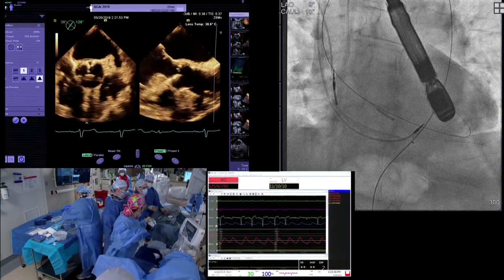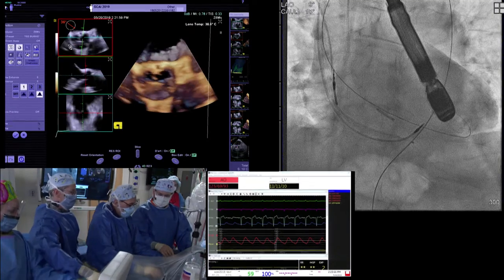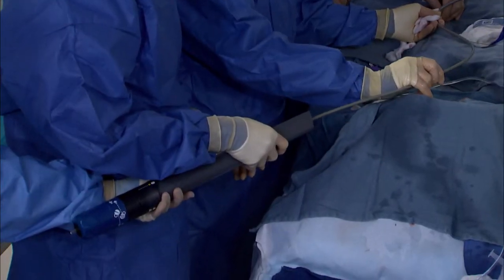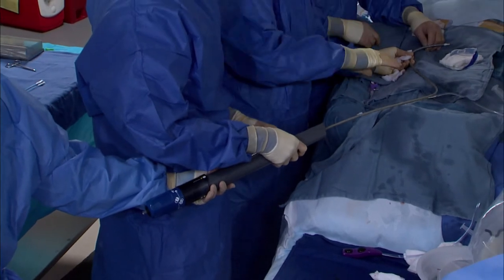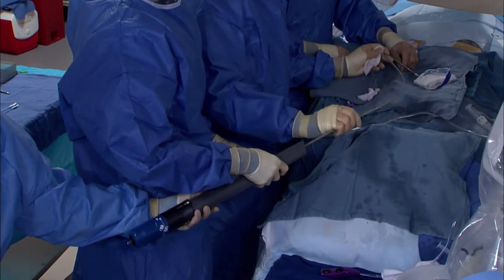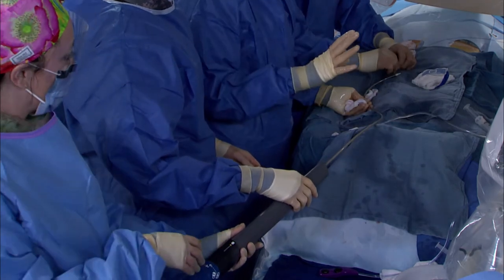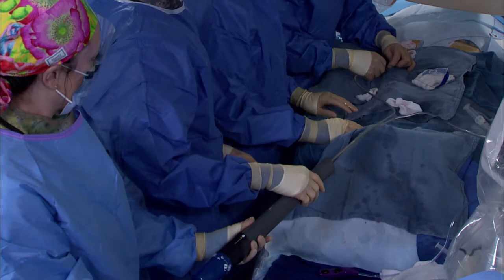While we load the Lotus valve, why don't we show the S-shape? On the right axis side, we try to have this form an S-shape to go in. If we were doing it on the left side, it would be a Z-shape. When you deploy on the right side, you try and do an S-shape. We'll talk through the things we look at as we're deploying.